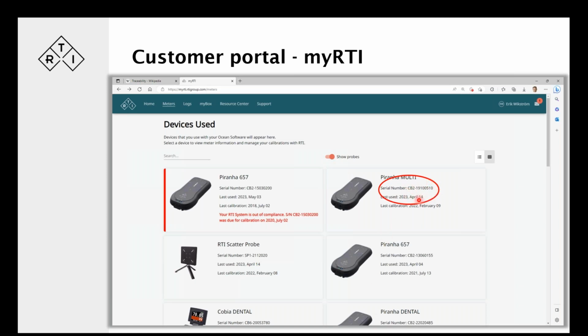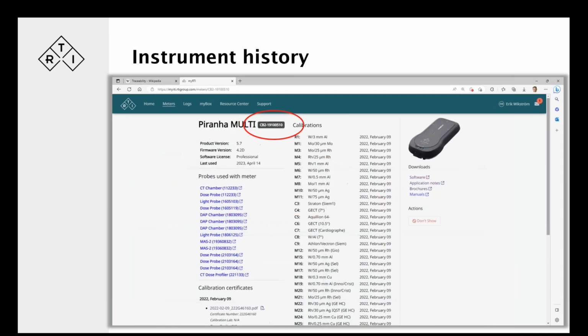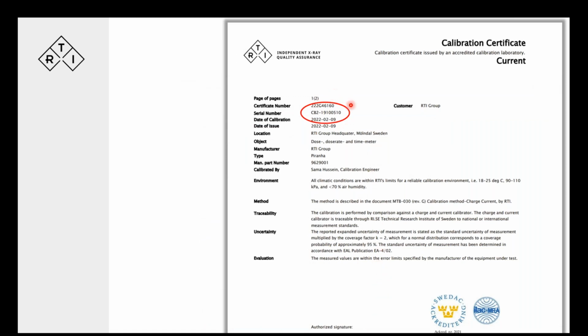And if you remember, we had this serial number, that's the one we were using. So if we click on that, we get more information about this specific serial number. Among that information we have calibration certificates. If we click on there, we get to a calibration certificate. In this case, it's the one for current, but all the calibration certificates are available. There we'll see when it was calibrated, where it was calibrated, what type it was, part number, who performed it, what was the environment, method, traceability. It's traceable to ri.se, which is a Swedish research institute, a Swedish NIST, so it was performed here in Sweden. But it's traceable to national and international measurement standards.